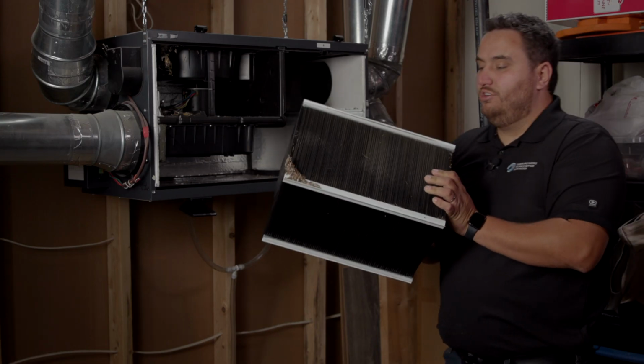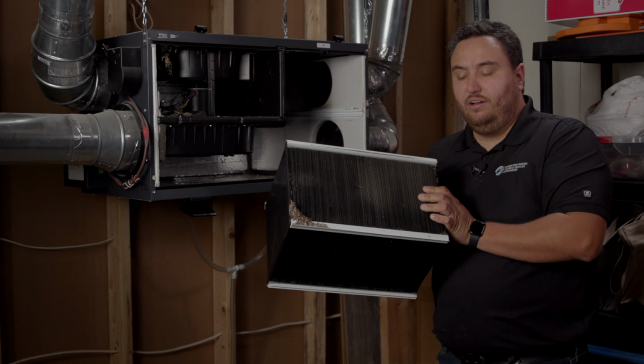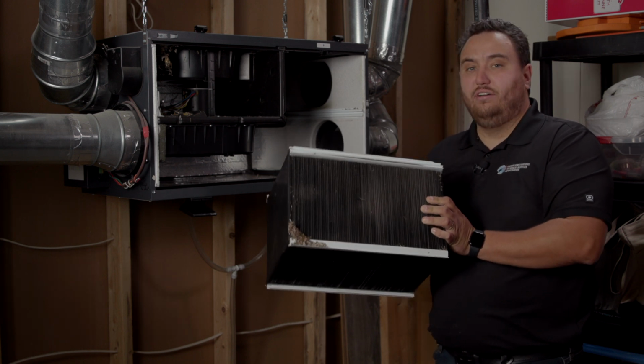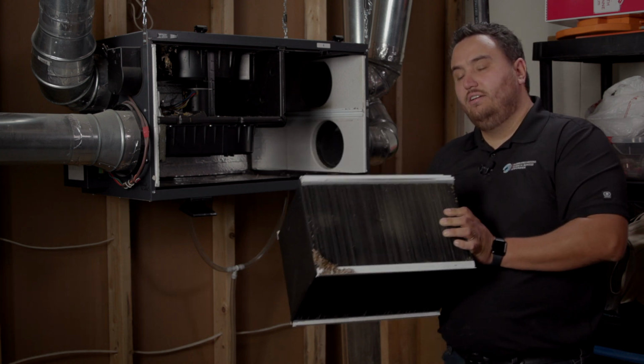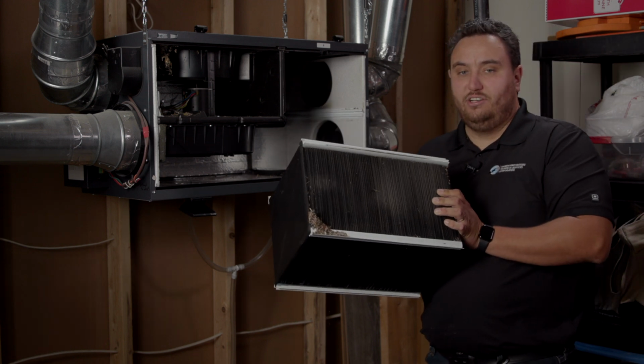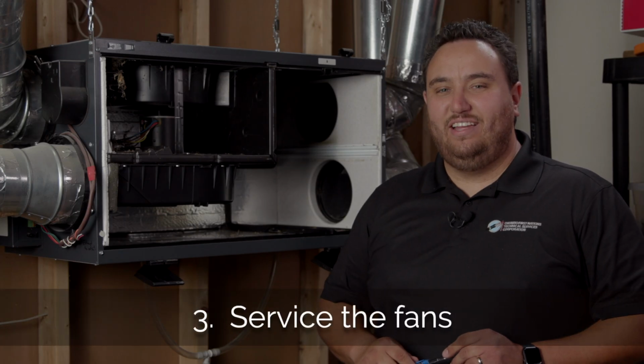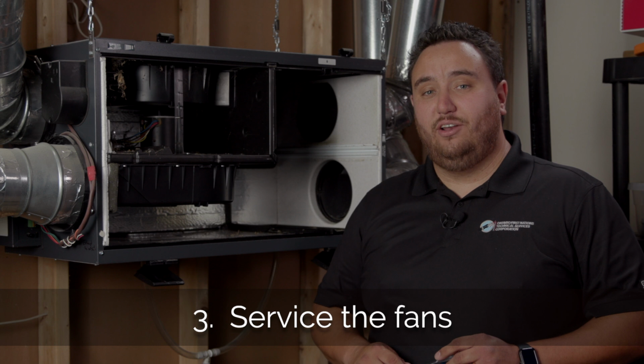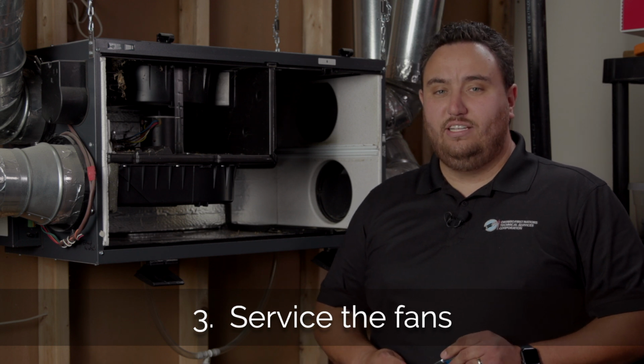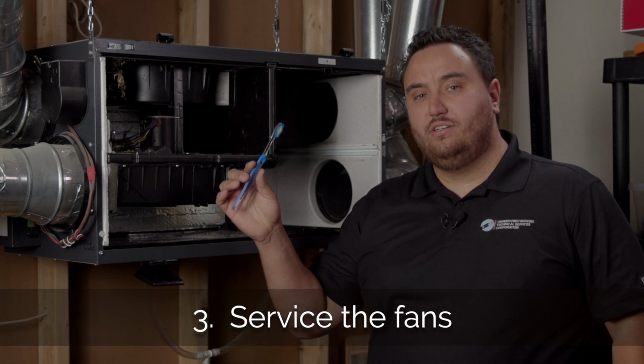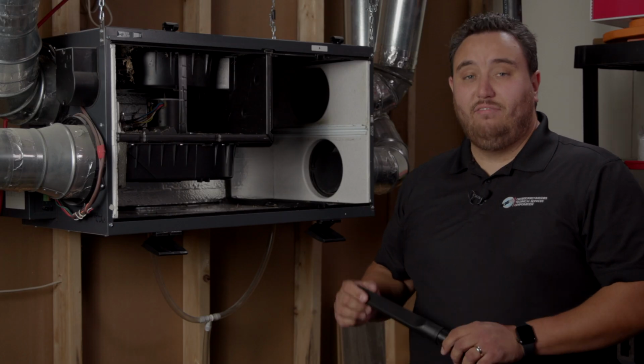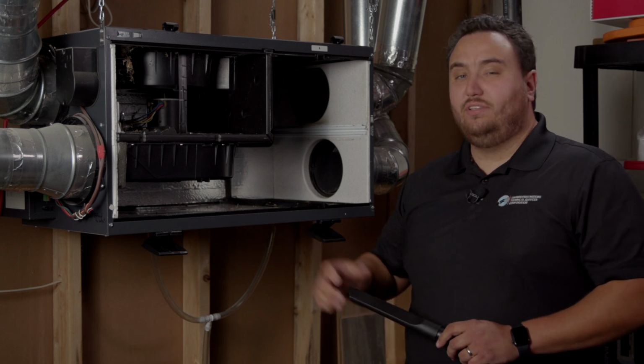The heat recovery core should be removed and washed once a year. Let it soak in warm water and mild detergent. Let it dry completely before putting it back inside the HRV. Newer HRVs would have fans that require little to no maintenance. Older HRVs may require cleaning with your toothbrush, or fans that require lubrication. Make sure to check your owner's manual for more information. Now I got my vacuum all set up. We're going to vacuum out the inside of the HRV, and I'm also going to vacuum the filters.